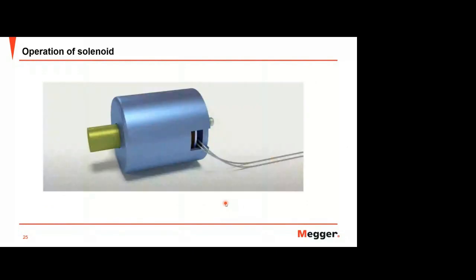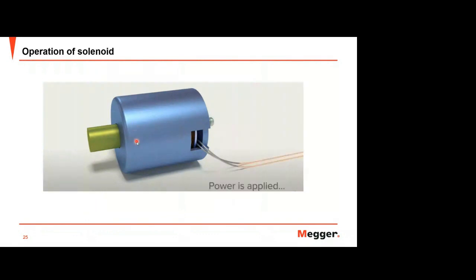And this is the operation of a solenoid. Why am I trying to explain this? Because when we talk about the tripping coil, basically the principle of the tripping coil works similar to the solenoid. When you give voltage to the solenoid, the current will flow through it, and the current will move the armature or plunger. The plunger will move in some direction, either right or left, depending on the current direction you apply to the solenoid.